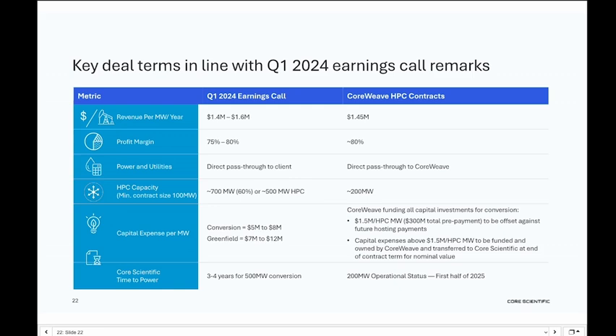We've also communicated a range for CapEx. All investments are ultimately going to be paid by CoreWeave, but when we set the stage in May, we shared that the conversion is between 5 to 7 million per megawatt for conversion, and a greenfield project is between 7 and 12 million. What's critical, and as Adam suggested, we want this to come across loud and clear, is that CoreWeave will fund all investments associated with the build-out costs for that 200 megawatts.